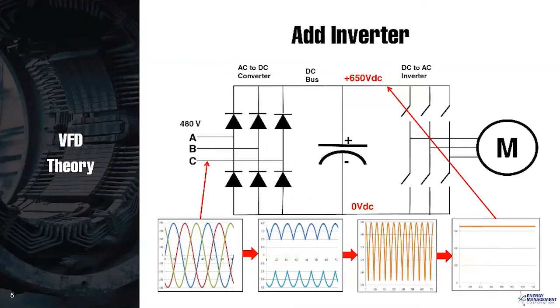Now this slide shows the inverter. Now we're going from DC to AC. And I'm showing 6 switches. Of course, in a real drive, as we talked about before, these would be IGBTs. But that's all an IGBT is functionally in the drive. It is a switch. It turns on and off to create the output waveform.